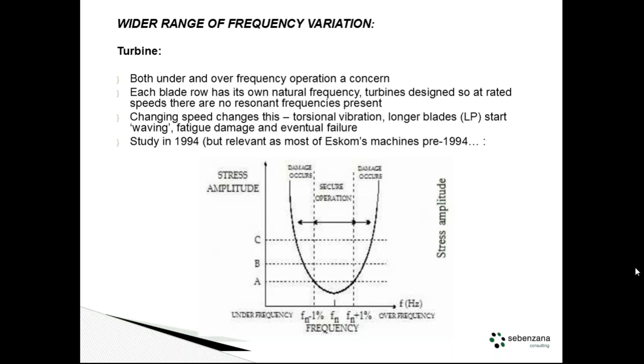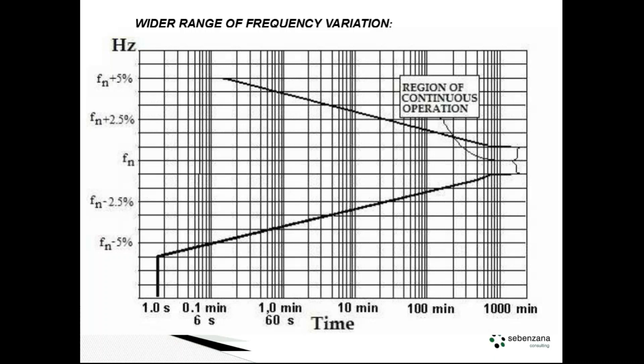We've talked about grid code discussions with the generator guys, electrical guys, the distribution networks — but are you talking to the turbine people as well? From that same study, continuous operation is only just under 1% either way. When you look at what the grid code is looking at — at 6% I think it was — I'd probably accept that for a second or so before you start having problems in the turbine. But these guys are talking 20 seconds or up to minutes. There are potential problems there.